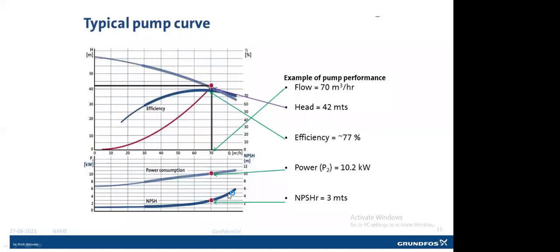So our NPSH available at site should be more than 6 or 7 meters. And if sufficient NPSH is not available at site, the pump will start to cavitate. And at that time, what do we do? Since the pump is operating at a higher flow and it is cavitating, we try to throttle the valve and reduce the flow to bring the duty point into the required NPSH zone, or to get the required flow, which affects the system performance. How it affects, we'll discuss one by one.